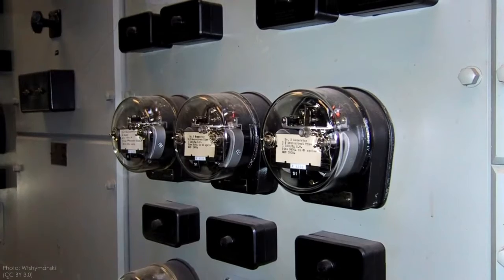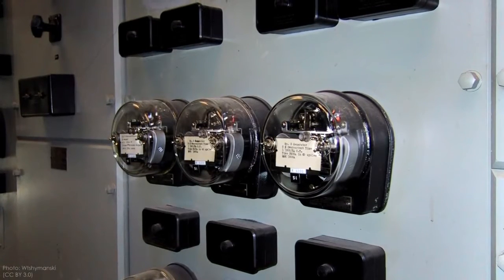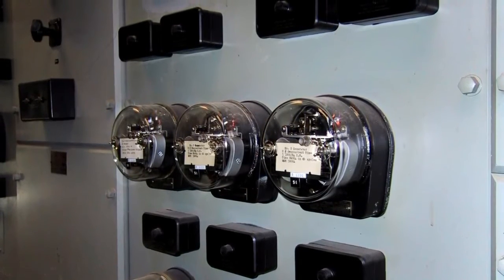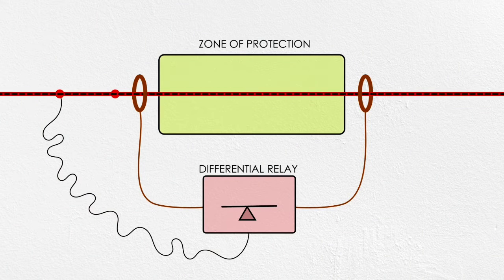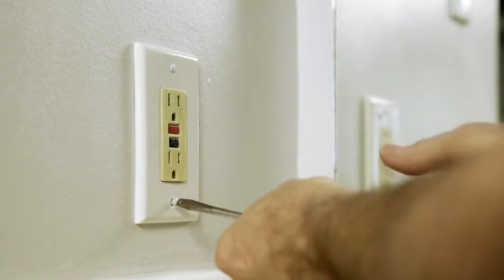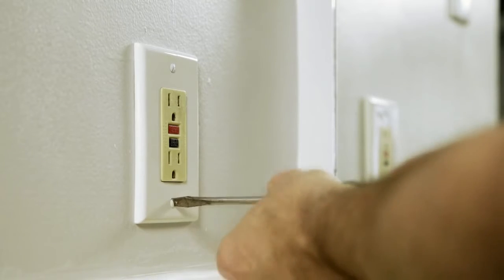Protection on the grid is primarily done through relays that can measure all kinds of parameters to identify faults and activate circuit breakers, which isolate equipment and notify the utilities of the problem. These relays are measuring voltage, current, and power on the lines, just like you'd expect. They also measure differential current. Even if the current isn't too high, you want to make sure that as much current is going out as is coming in. Otherwise, you're losing it somewhere else, which can be a signal of a fault. This is the same principle that GFCI outlets in your house use.